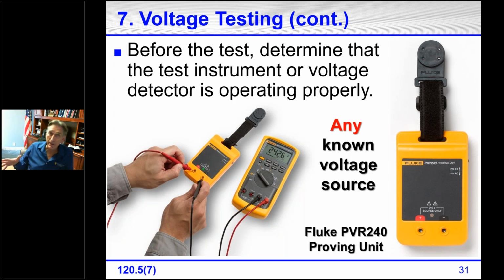So if you turn off all the power in a certain area, you can use any voltage to test your meter. You could use a 9-volt battery, a AA battery. It doesn't matter. Most meters, though not all, if you're checking DC, you have to change the dial. Check AC, you change it back to the AC setting. Checking DC again, you change it back. I'm a bit cautious when I talk to people about this. It is permitted, but there's a potential for human error there, putting the meter in the wrong setting.